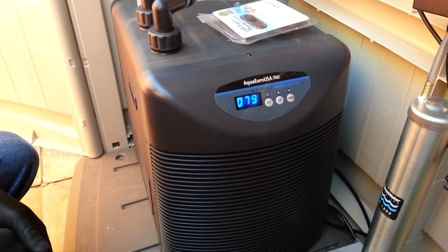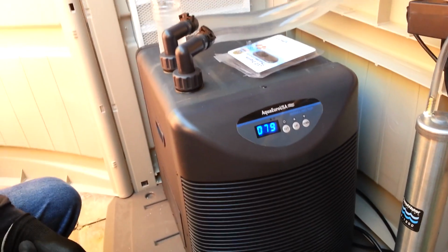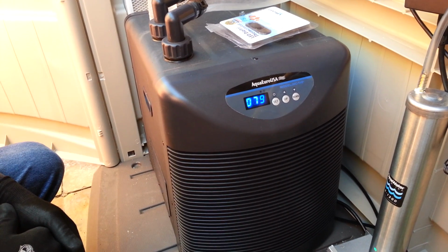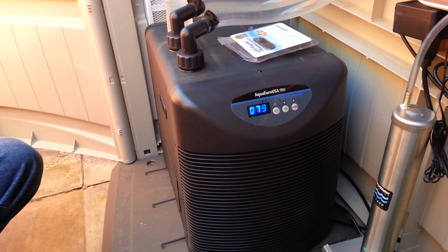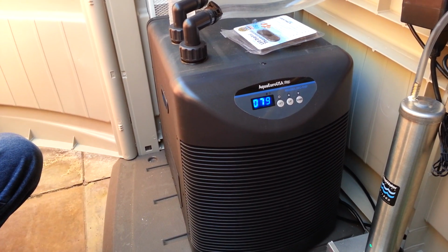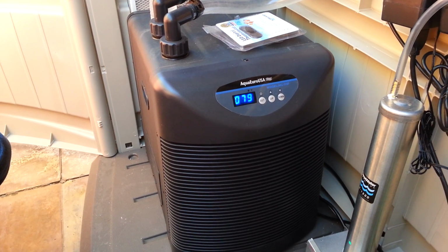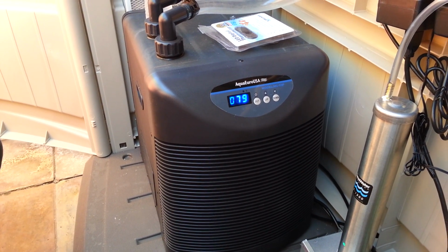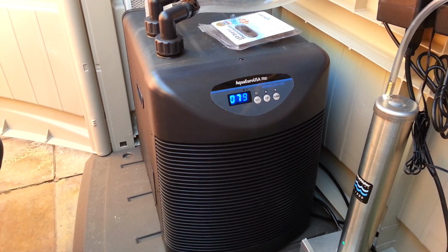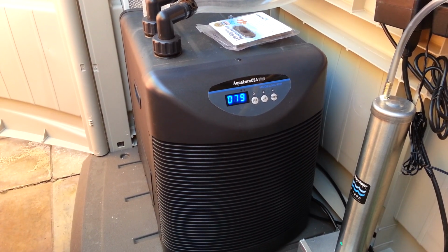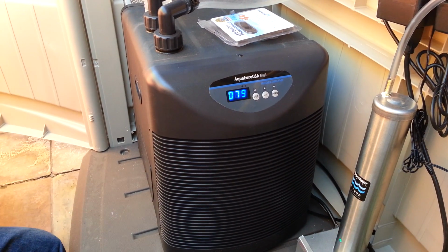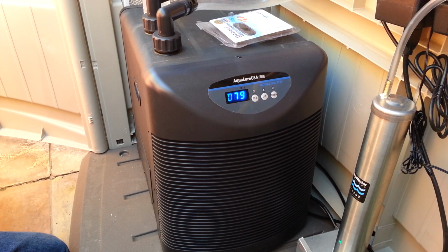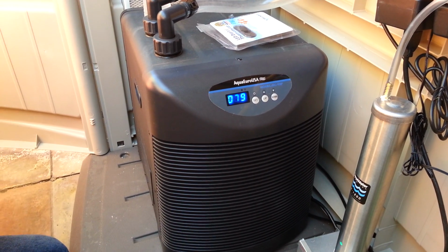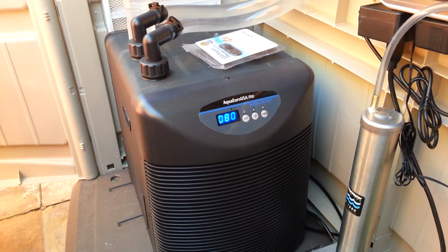Okay, so the chiller just came on, and now it's running. Everything's equal. The pump's going through the chiller. That's not stopped. The temperature's been 79 on there. Temperature's still the same on there. Okay, now the chiller will start running. You would expect it to cool the water. And there you go, it goes up.